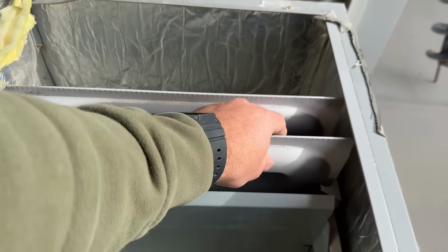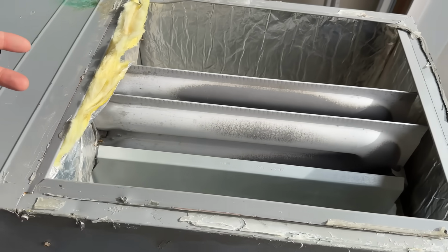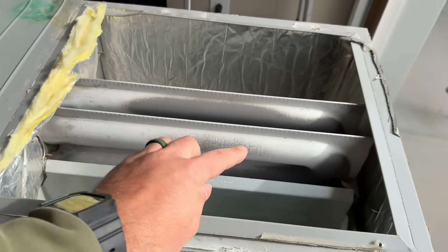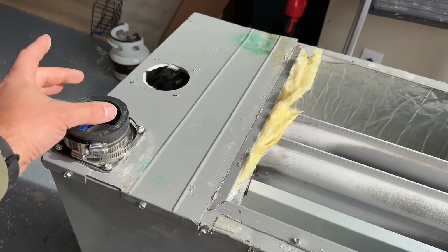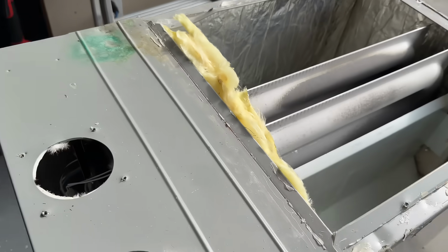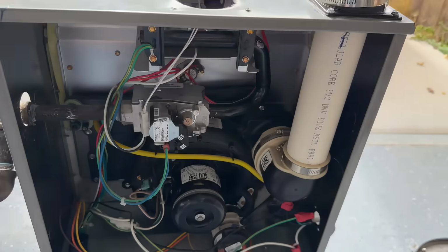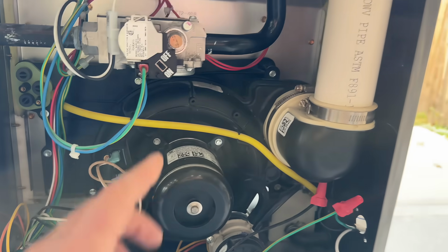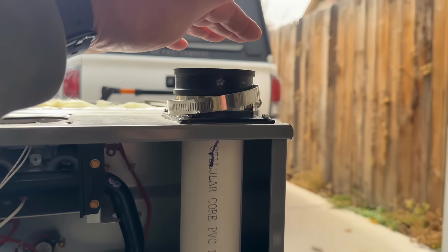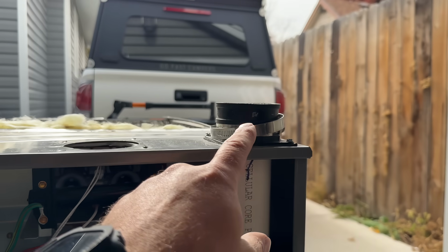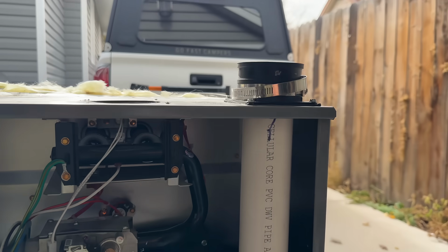So it's just this right here. And those flames are going to go through there, and it's going to get sucked through the heat exchanger, and it's going to spit out the exhaust right here. Okay, so our blower turned off, the inducer motor is on, so it's actively pushing air out of here. And this right here is where you would vent to the exterior of your home.